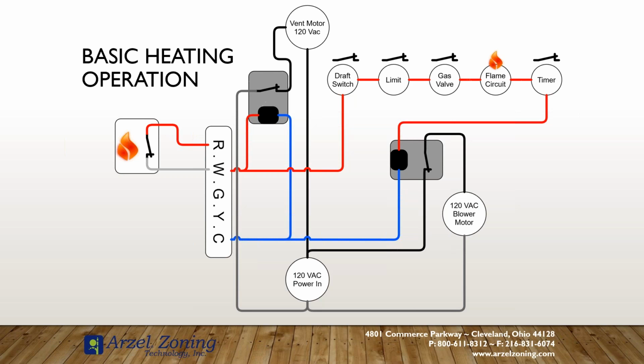However, that doesn't change the very basics of it, because there's a draft switch that has to close to prove my vent motor's running. There's a limit switch that has to be closed to allow my gas valve to start. There's a flame proving circuit that has to prove that my gas valve is actually working in order for it to keep energized. And then once that's proven, I have a timer, my blower starts, and I get heat going to my home. So when we start taking it back to the very basics, it makes the diagnosis a lot easier, because as we work our way through the process, we're able to find those failures and diagnose them effectively for our customers.